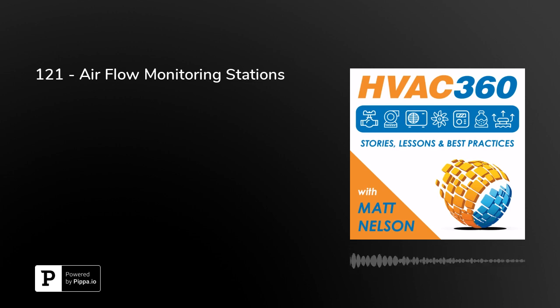All right. So one thing that you have to remember is that more sensing locations really improves your accuracy. More sensing locations, better average, makes sense, right? Also, this is, again, getting back to those VAV box flow rings. These are some of the devices that you're going to find already come with, and they're usually more the velocity pressure variety. They're going to come with flow rings.